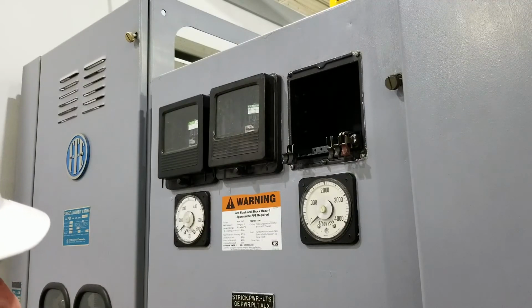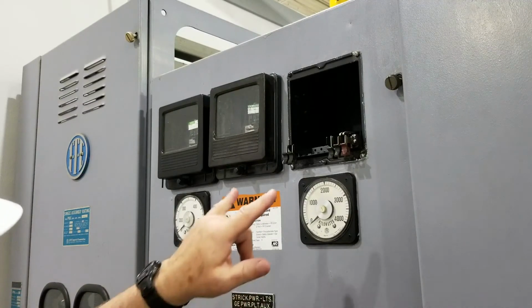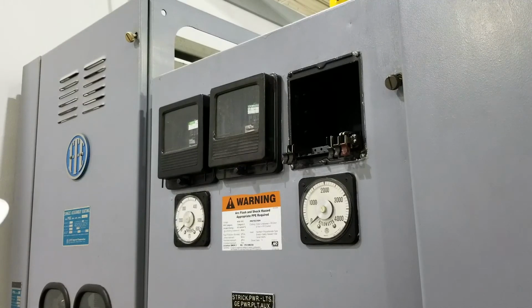If we've opened up the circuit breaker, in the most likely scenario the AC has been removed. But the DC is completely separate and independent of the AC, and unless we've somehow removed the DC by doing something with the battery voltage coming in, there could still be hot DC in that can. Be careful, don't stick a screwdriver or any metallic object in there - you could easily short out your battery bank and cause some real problems.